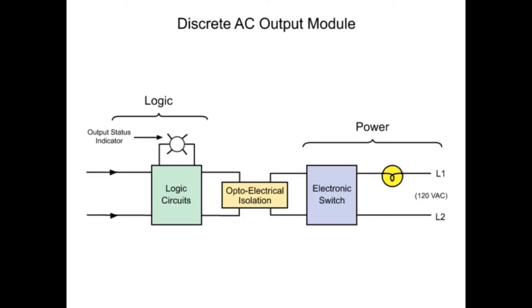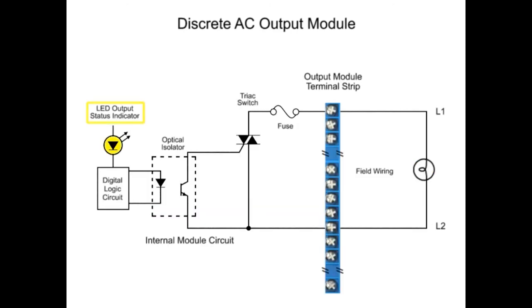For the AC output module, the circuit is comprised of a power section and logic section, coupled by an isolation circuit, similar to the input module, but in reverse order. When the output status is commanded from the PLC program, voltage is transmitted to the LED of the optical isolator.